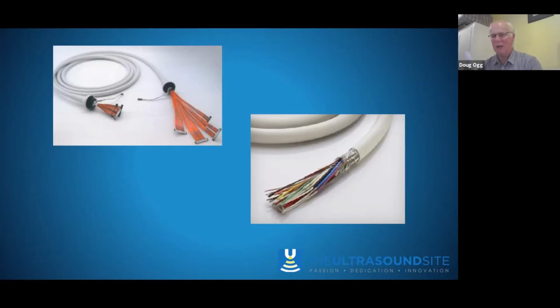Sometimes manufacturers will put a little bit of processing, a little bit of amplification into the system before the electricity leaves the probe. Because if you can do that, then that boost helps to reduce the effect of crosstalk and poor connections. But poor connections are a really, really troublesome factor in ultrasound, because these voltages are absolutely tiny. Yeah, yeah.